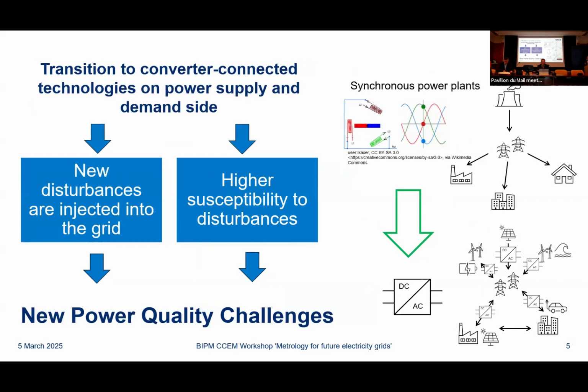But everything's changing, as we've already heard today. We're moving towards a grid that's going to be much more dominated, in many places, by converter connected technologies on the supply side, but also on the demand side. And today I'd like to highlight two big changes that affect power quality as a consequence. One is that we've got new disturbances being introduced into the grid, but also the susceptibility or the sensitivity of the grid to those disturbances is changing. And in combination, that leads to new power quality challenges, and the methods that I just showed that are existing are not fit for purpose to manage all of these novel effects.